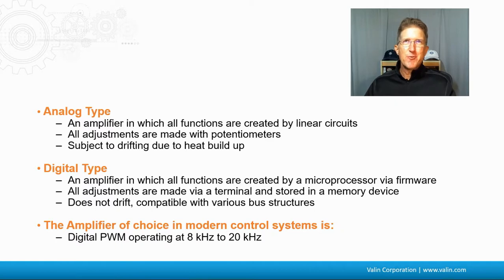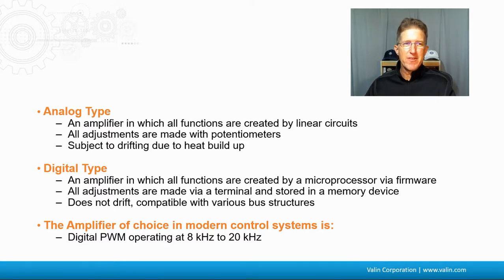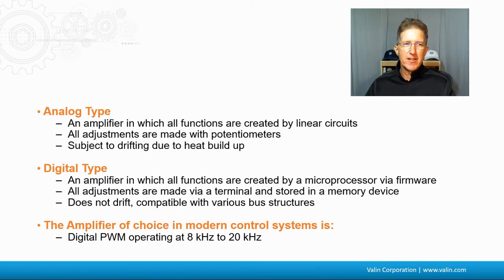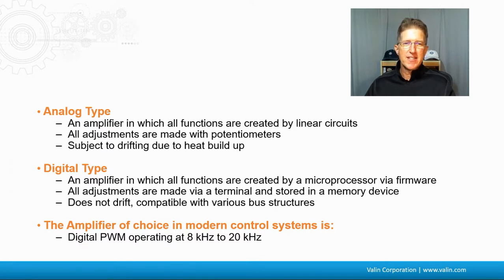When I started in this industry about 23 years ago, analog drives were definitely predominant — there were very few digital drives on the market. Analog type drives have all their electronics made by linear circuits, and adjustments are made with potentiometers, so they can drift a little bit and you have to use a screwdriver to adjust. Digital type drives have their functions created by microprocessors via firmware, and all adjustments are made via computers and software. It doesn't drift, so it's compatible and can be used with a lot of different communication bus structures and protocols.